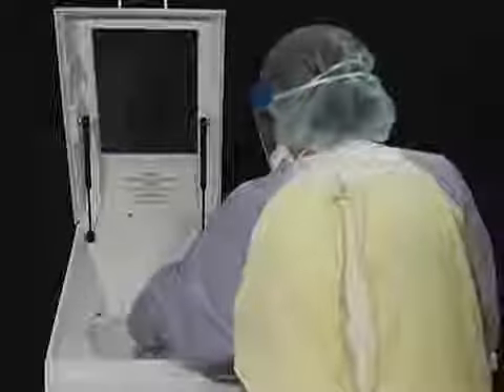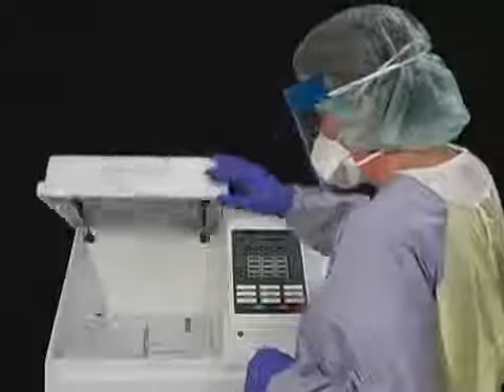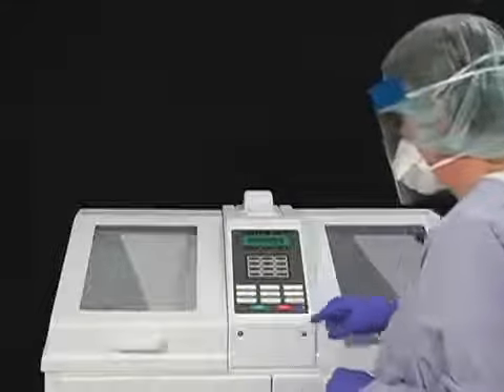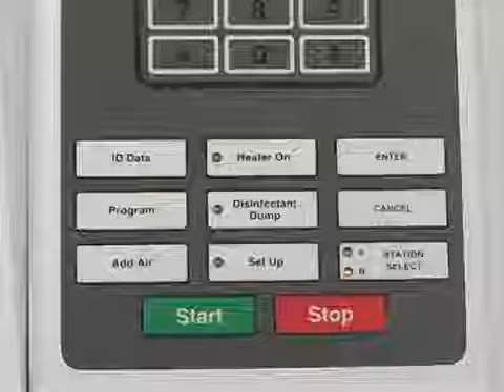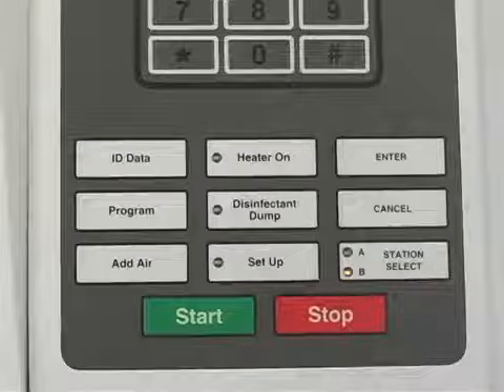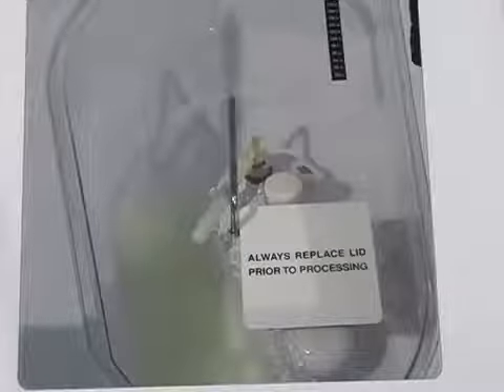Ensure that the restrictor connector is snapped into the connector port. Press the appropriate Station Select function key for the station where the disinfectant will be changed. Press the disinfectant dump key, then Start. The DSD will prompt the user to attach restrictor. Ensure that the basin restrictor is snapped into the connector port before pressing Start again to drain the reservoir of the selected station. Disinfectant is pumped out of the reservoir and into the basin. From the basin, it flows out the drain. This cycle takes approximately 8 minutes.